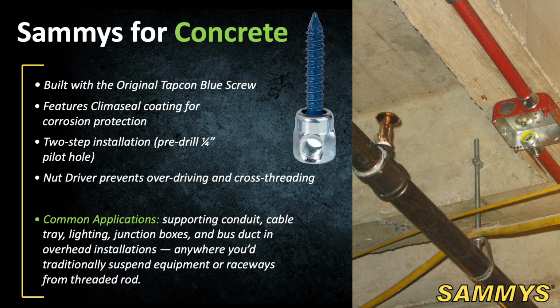Next, we have Sammys for concrete. These versions are built using the original Tapcon blue screw technology and feature a Climaseal coating for corrosion protection. Installation is typically a 2-step process. You pre-drill a 1/4 inch pilot hole and then drive the Sammy using the correct nut driver. Again, typical applications are supporting conduit, cable tray, lighting, junction boxes, and bus duct from concrete ceilings or beams, especially in parking garages, industrial buildings, or large commercial projects.